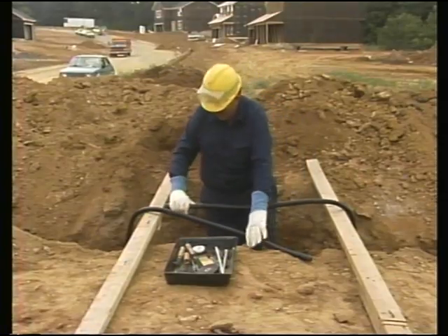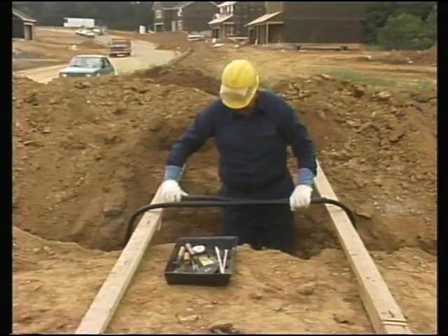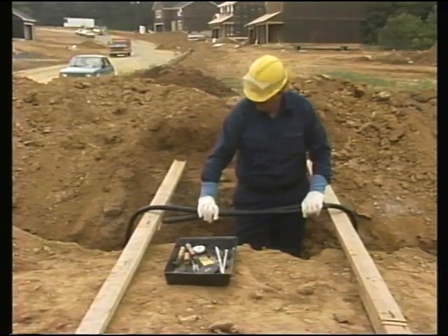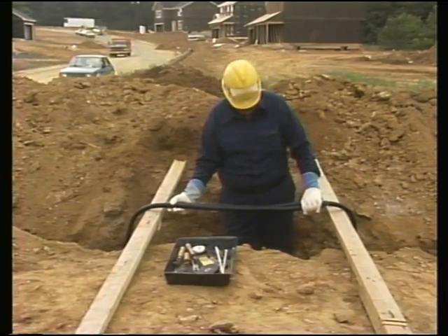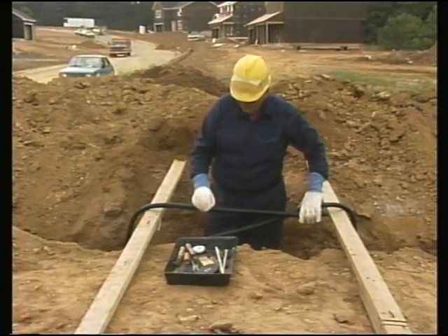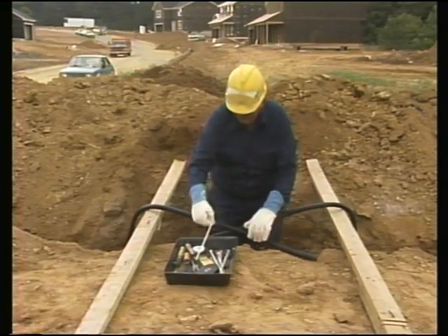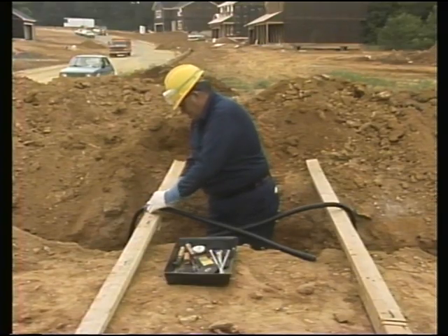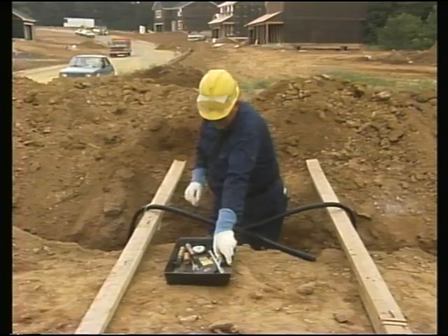In vault situations, for example, cables may be trained along a wall rather than hanging free to make the vault area more accessible. Secondly, training to increase the cable slack can reduce the mechanical strain placed on the splice area. Most splices aren't designed for heavy mechanical strains.